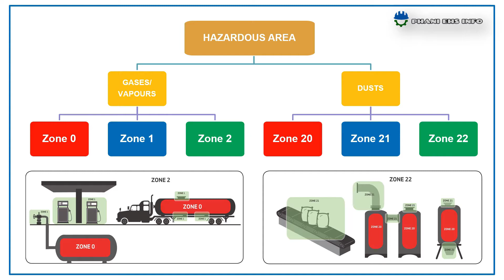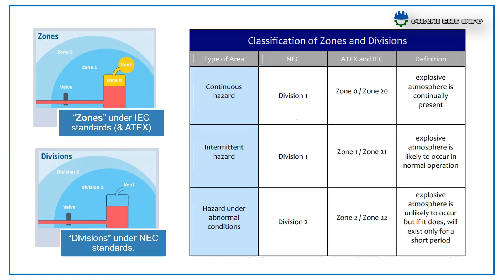Hazardous areas are classified in terms of zones and divisions. Zones under worldwide IEC standards, divisions under North American NEC standards, on the basis of the frequency and duration of occurrence of an explosive atmosphere. In Zone 0 or Zone 20, explosive atmosphere is continuously present for long periods or frequently. In Zone 1 or Zone 21, explosive atmosphere is likely to occur occasionally in normal operation. In Zone 2 or Zone 22, explosive atmosphere is unlikely to occur. If it does, it will exist only for a short period.